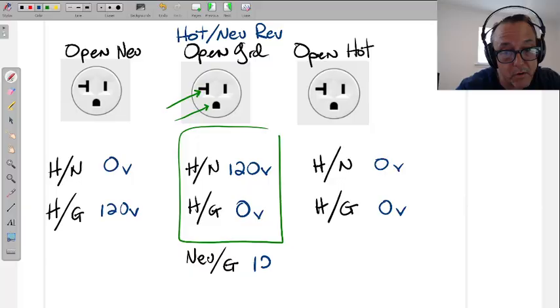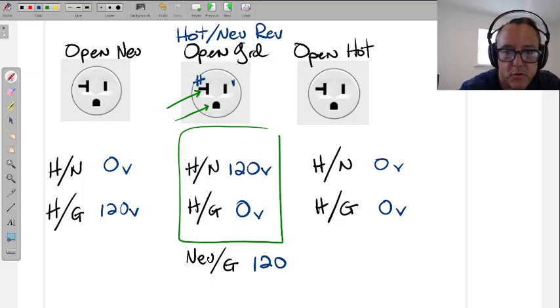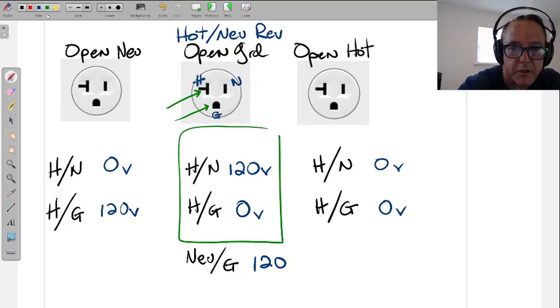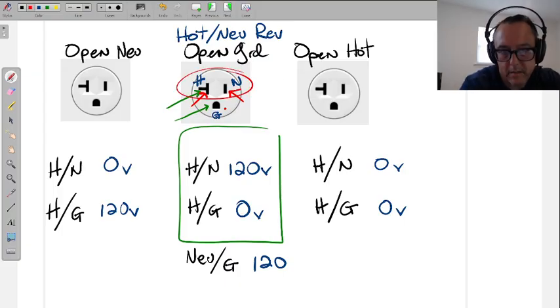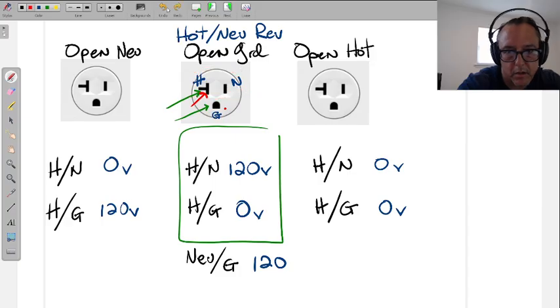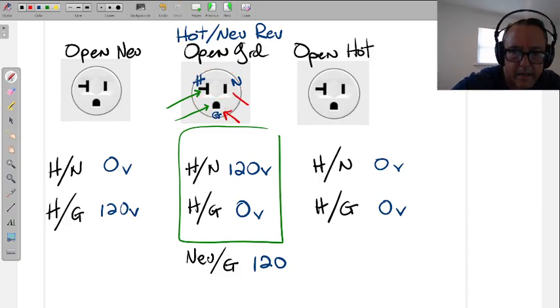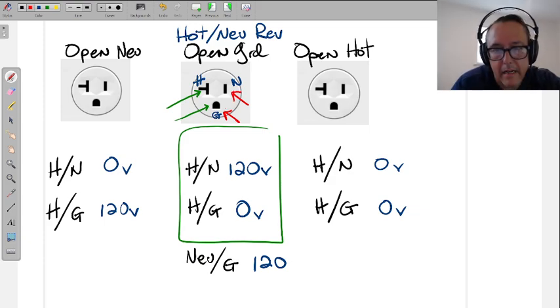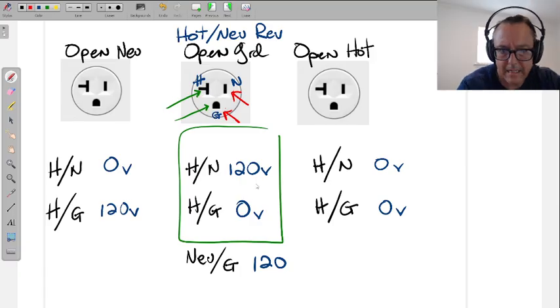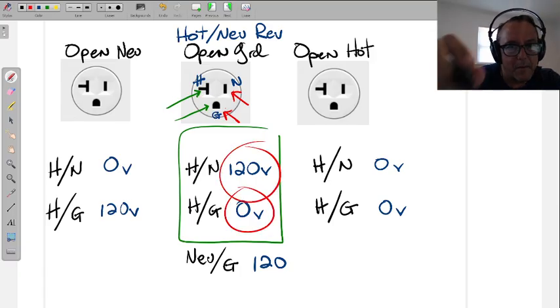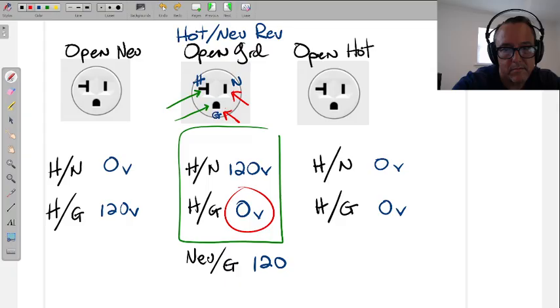Negative something, I don't know. 120. It's going to read 120 because the hot's sitting here, I've got my neutral over here, and of course the ground didn't change. So when I check between hot and neutral, I got 120 because there is a hot and there is a neutral, they're just in the wrong spot. When I check to see how the ground is doing, between what I consider the hot side of this outlet and the ground, I got 0. So now I'm thinking, oh well, there's no ground.